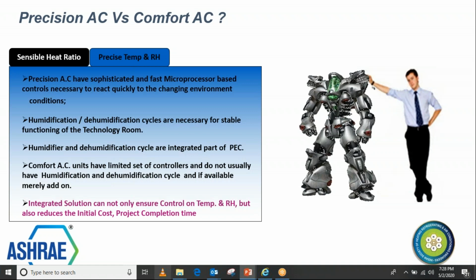Another big issue is that if your filtration is not good in the room, we see in many places in industrial applications PCB failures or failures of such critical components, just because over a period of time the component has a layer of dust accumulated, because of low filtration and because the humidity control was not good. This layer restricts the heat dissipation from that component. So although the component is installed in an air conditioning environment, it is not able to dissipate the heat. It gets heated up and then it fails. Most of the time we assume the electricity or the power quality was not good, but you never realize that there is a problem with the air conditioning working there.